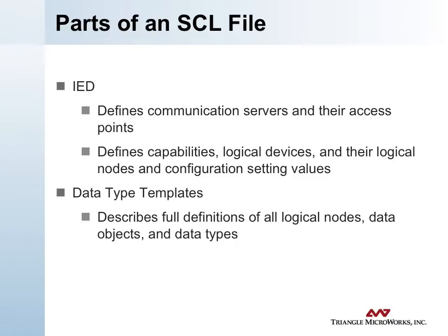The IED section of the SCL file defines the communication servers and their access points. These access points have references back to the communication section so that you can link up with the actual physical infrastructure. The IED portion also defines the capabilities of each IED, logical devices and logical nodes within those IEDs, as well as all of the initialization data for things like configuration parameters and settings for each IED.